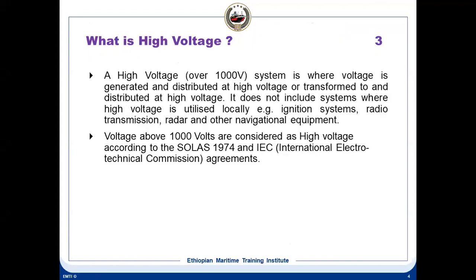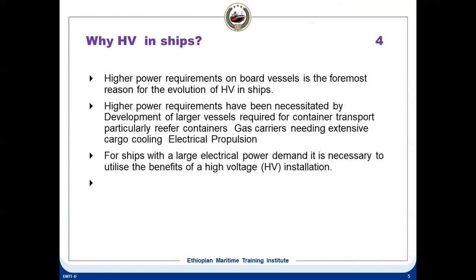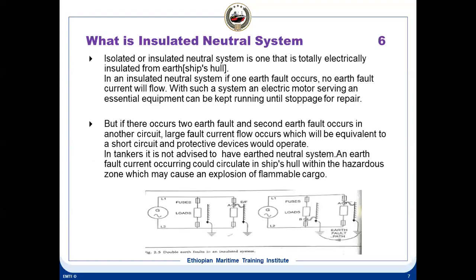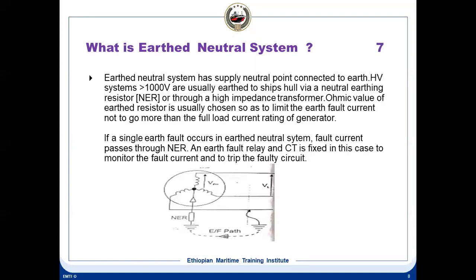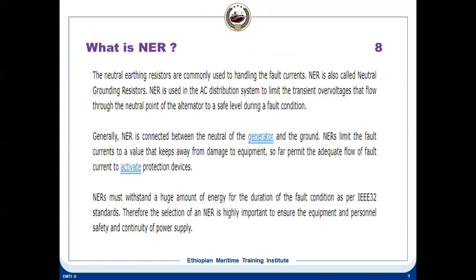What is high voltage? Any voltage above 1000 volts is considered to be high voltage. Why do we need high voltage on ship? Because of the power requirements. What are the equipments covered under high voltage? Then what are insulated neutral systems? Very important. What are insulated neutral systems? What is earth neutral system? Difference between earthed neutral, insulated neutral, isolated neutral, advantages, disadvantages.